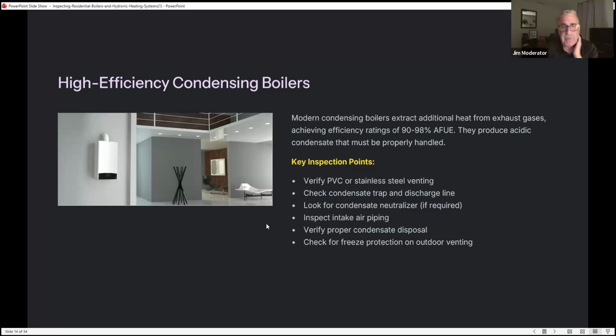But Scott, question for you. For newer inspectors, when you go see the unit on a high efficiency condensing boiler, how do you determine that it's a high efficiency condensing boiler and that it may need or require a neutralizer? Well, how it's vented too, because now you're reusing a lot of those flue gases. So if you see a pipe going out, sometimes you'll see concentric. If you look on the outside, you'll see a sidewall vent, or you could see a gooseneck, one up, one down, one's intake. I can't even do it on here. One pipe is exhaust, one is intake. If you see that, it's a condensing boiler. If it's going up the chimney, natural draft, then it's not.